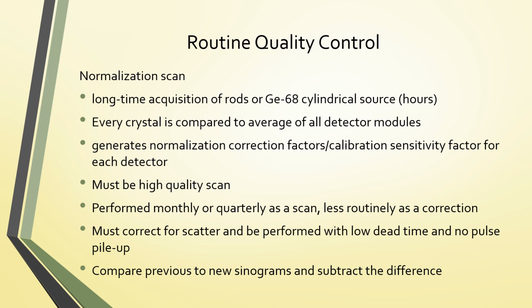It can be performed monthly based on some recommendations from the manufacturer. Mostly it's performed quarterly and less routinely as a correction. It must correct for scatter and it must be performed with low dead time and no pulse pileup. And it should be compared to previous and new sinograms and then subtract the difference.